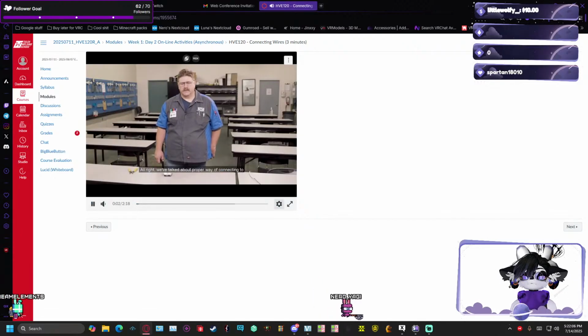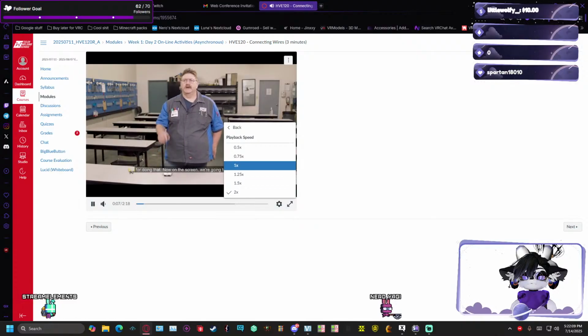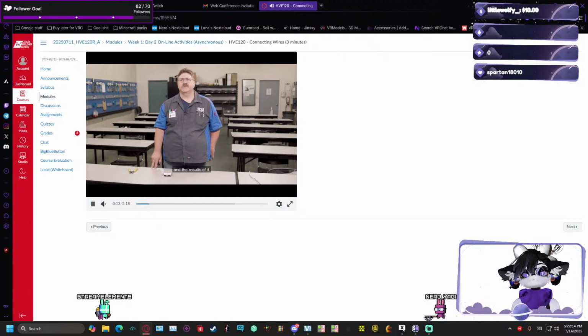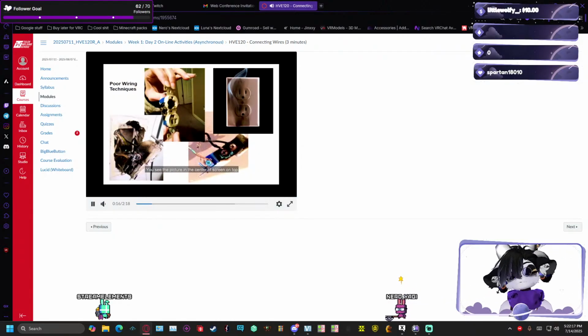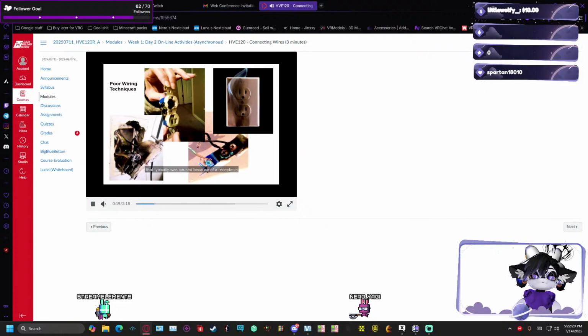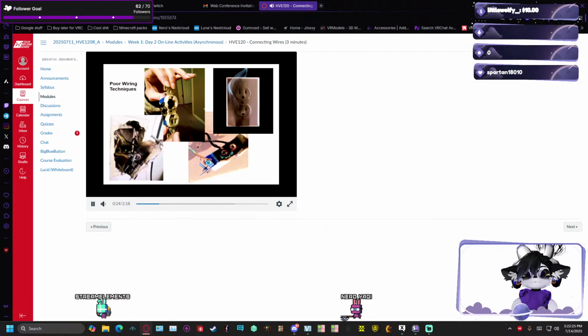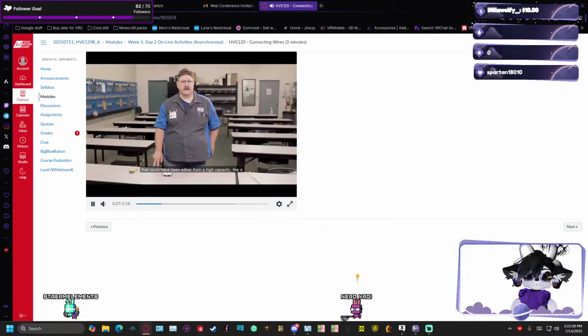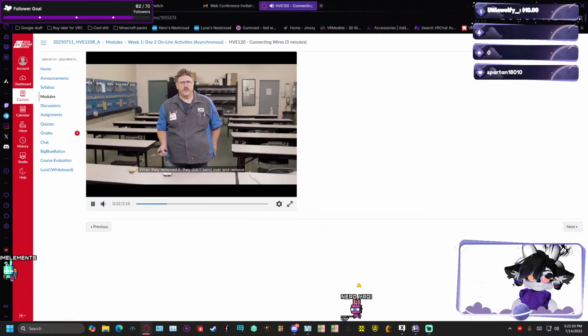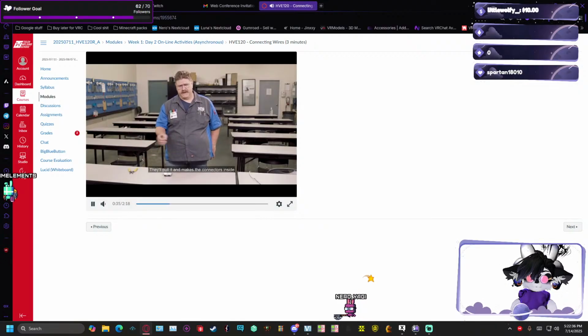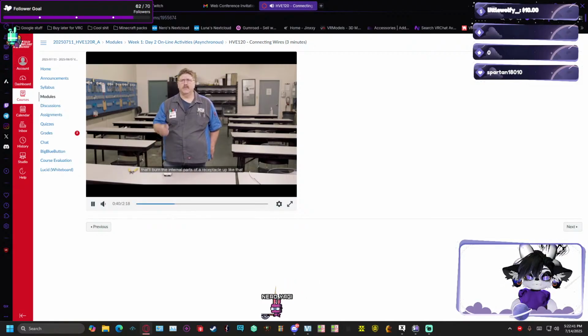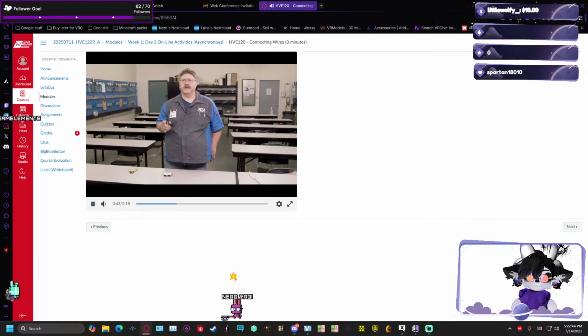All right, we talked about a proper way of connecting to a duplex receptacle and proper technique for doing that. Now on the screen, we're going to show you a couple examples that weren't done correctly and the results of it. You see the picture in the center of the screen on top? That typically was caused because of a receptacle that was worn out internally, and that could have been from a high ampacity load, like a vacuum cleaner or something like that. When they removed it, they didn't bend over and remove the plug properly. They'll pull it, and it makes the conductors inside poor contacts, and that'll cause a resistive connection, and that'll burn the internal parts of a receptacle up like that picture in the center.